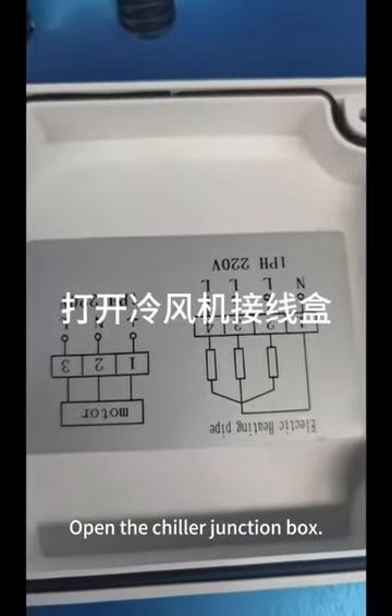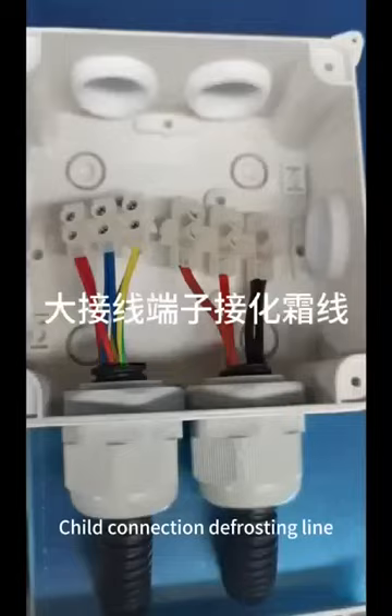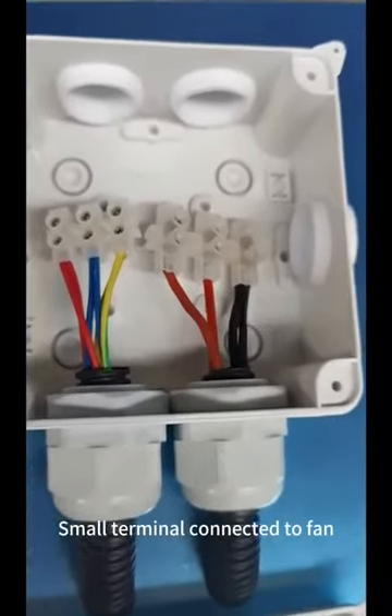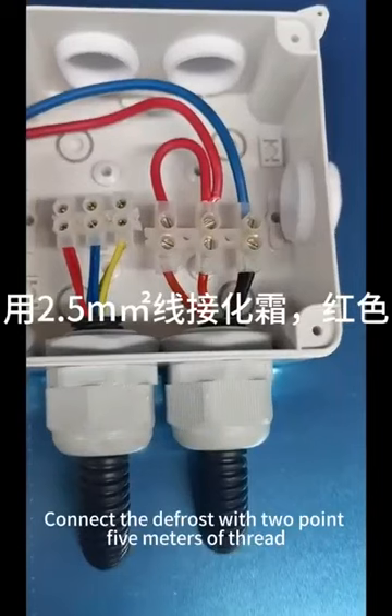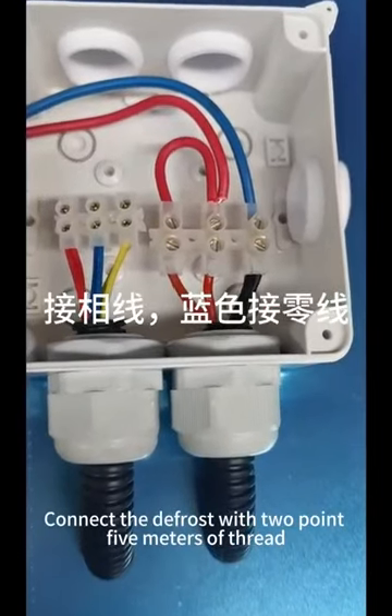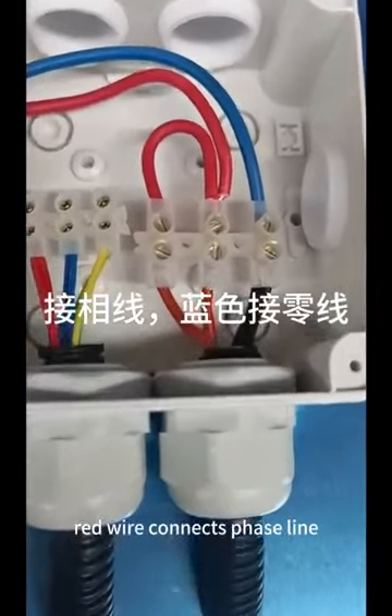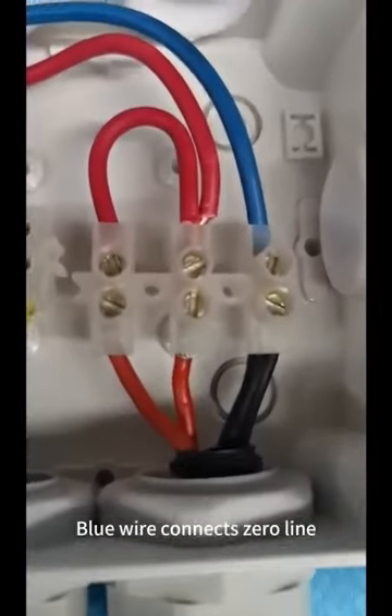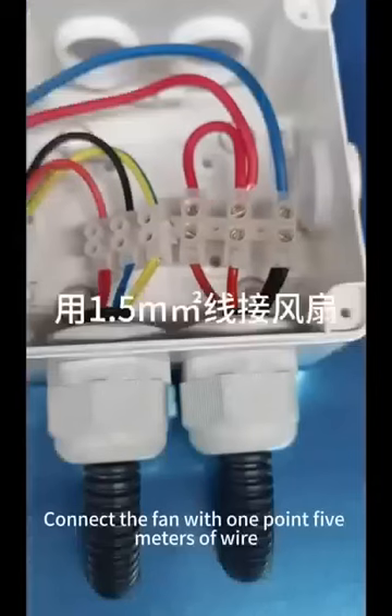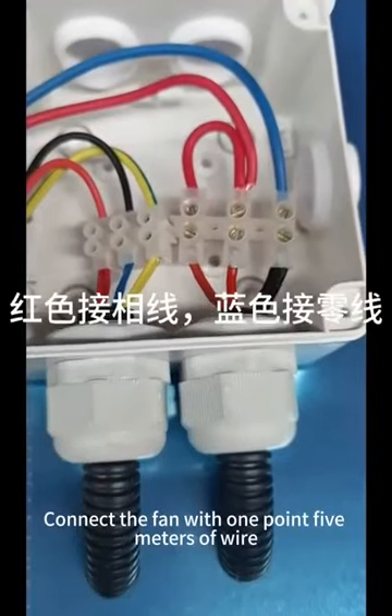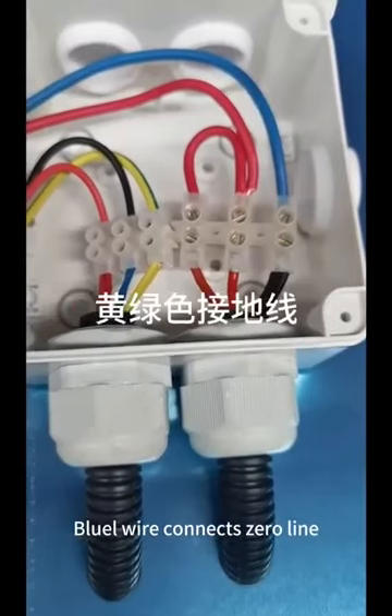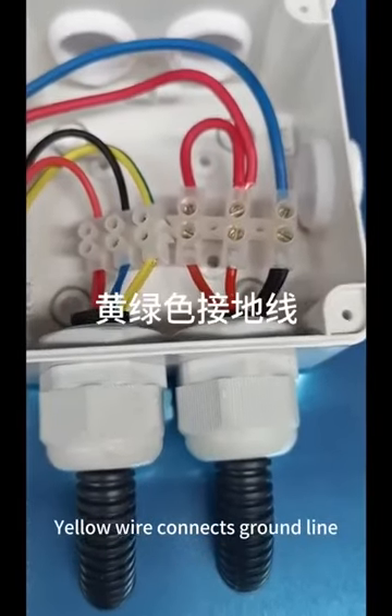Open the chiller junction box. Understand the wiring diagram. Connect the defrosting line. Small terminal connected to fan. Connect the defrost with 2.5 meters of wire. Red wire connects phase line. Blue wire connects zero line. Connect the fan with 1.5 meters of wire. Red wire connects phase line. Blue wire connects zero line. Yellow wire connects ground line.